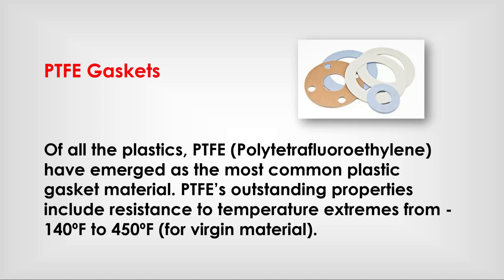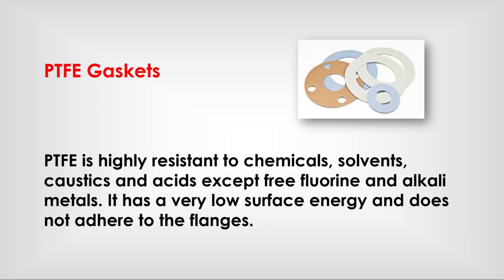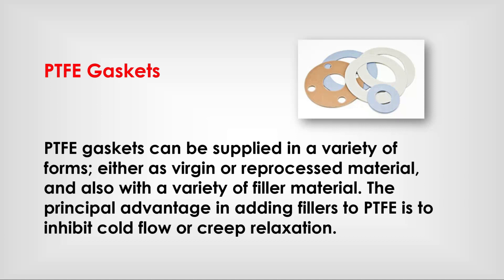PTFE gaskets: of all plastics, PTFE has emerged as the most common plastic gasket material. PTFE's outstanding properties include resistance to temperature extremes from -140°F to 450°F. It is highly resistant to chemicals, solvents, caustics, and acids, except free fluorine and alkali metals. It has very low surface energy and does not adhere to flanges. PTFE gaskets can be supplied in various forms, with a variety of filler materials; the principal advantage of adding fillers is to inhibit cold flow or creep relaxation.